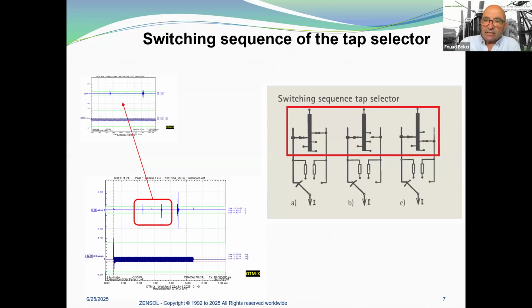With an OLTC comprising a diverter switch and the tap selector, the tap operation takes place in 2 steps. Here you have the switching sequence of the tap selector. In fact, you have 2 mechanisms that could move, the selector and the diverter. The next tap is first pre-selected by the tap selector at no load. Here you have the initial position, and we have to move to the second one. At the end of the switching sequence, the tap selector has moved.